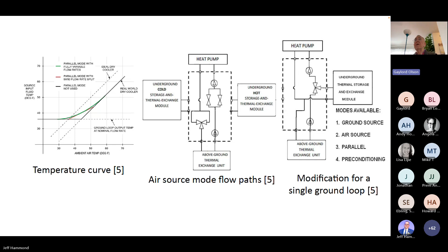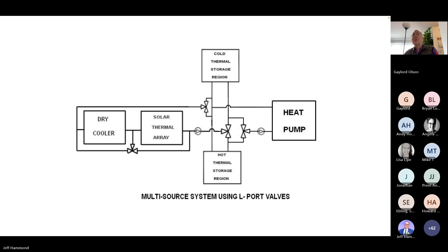So this is a little bit more capable type of system where you can have solar thermal and a dry cooler. And this would be for a northern climate, I think, where the solar thermal does some real good. But the dry cooler can put cold water into the top ground loop for preconditioning. The solar thermal array can put very warm water into the bottom ground loop for preconditioning that. And these can all be what are called L-port valves, water source heat pump. Okay, moving along.